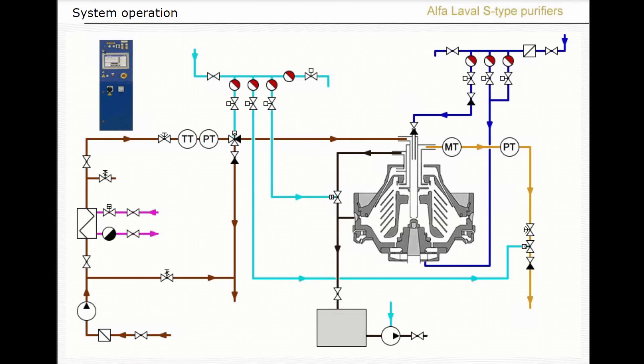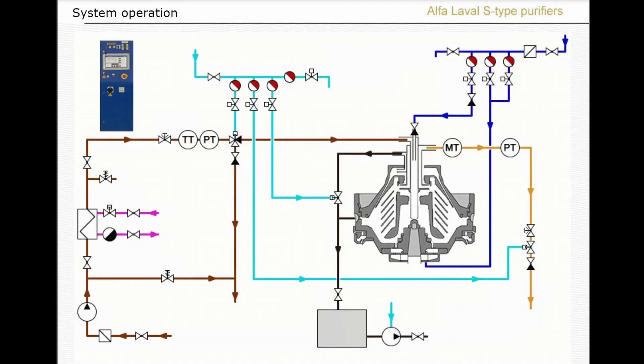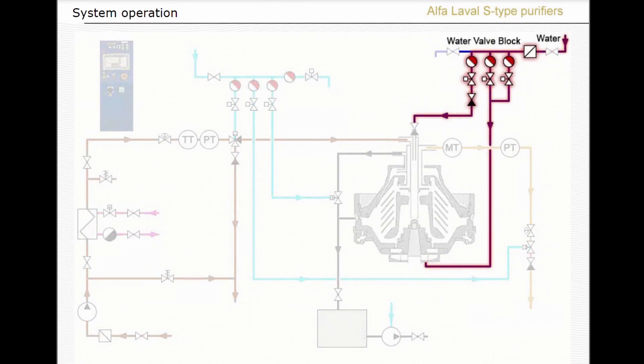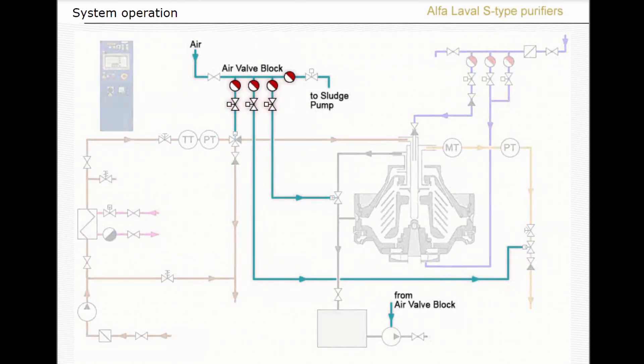In the meantime, the water accumulated in the separator bowl can be removed to the sludge tank by the water drain valve, which, as you have learned, opens according to the signal from the water transducer. The water valve block supplies conditioning water to the bowl interior and operating water to the bowl opening and closing mechanism.